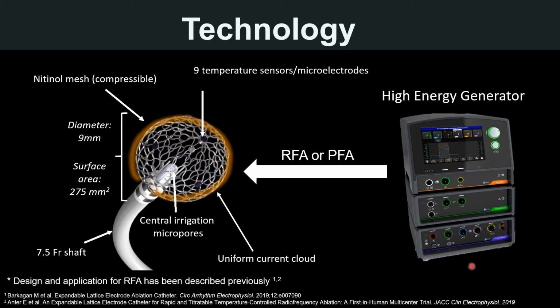The system includes a generator that can produce either RF or PF energy, and a bidirectional catheter with a shaft of 7.5 French. The catheter has a lattice tip electrode with both mapping and ablation capabilities. The lattice tip is made of a compressible mesh that expands to a 9 mm sphere once in the body. The sphere has 9 microelectrodes distributed evenly on its surface that act as thermocouples during RF ablation. The catheter also has an irrigation system through central micropores.